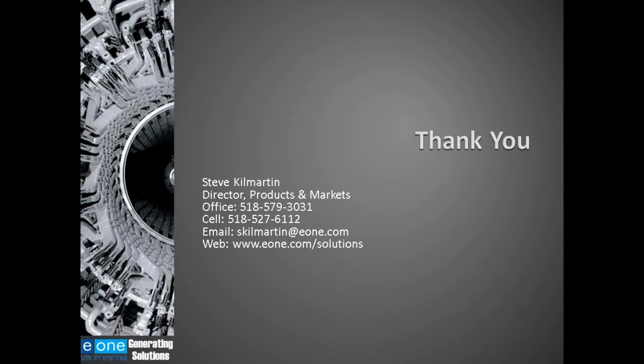Thank you, Steve. That was very informative. We have questions coming in. One of the first questions was: why not helium as a cooling gas? I believe hydrogen is more readily available than helium and costs less. Another question: is there any temperature monitoring for CO2 as it enters the generator? I'm not aware of any, though CO2 vaporizers do have temperature sensing. However, if you put CO2 into a generator too quickly, it could thermally shock the generator by cooling components too rapidly — so it's not a bad idea to monitor.